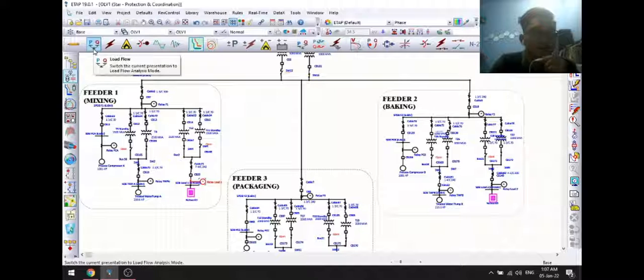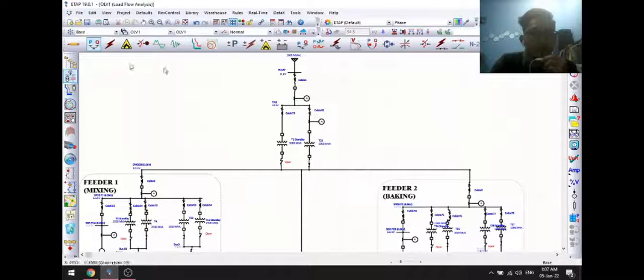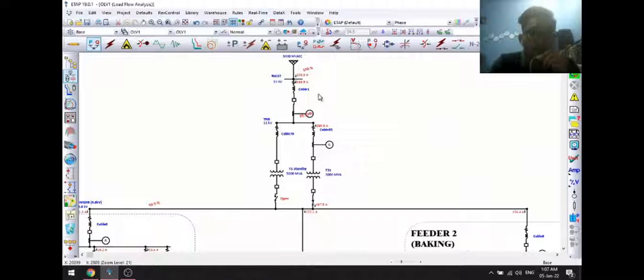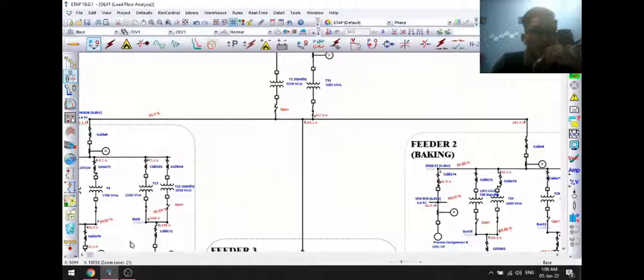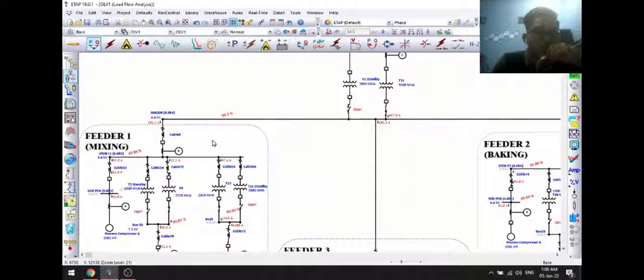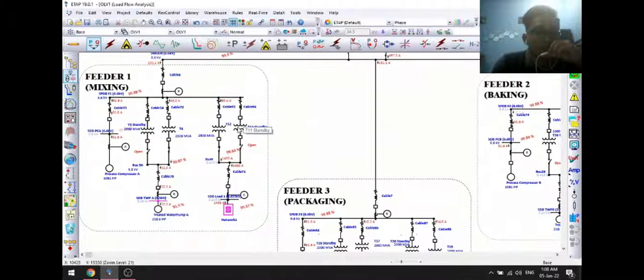For the power flow analysis, from the TMB we will receive 100% of voltage. Then when it reaches SMGDB, there is a voltage drop to 99.9%. And for each feeder, the lowest is 95.5%. However, it is still considered in good condition because the voltage drop is not more than 10%.